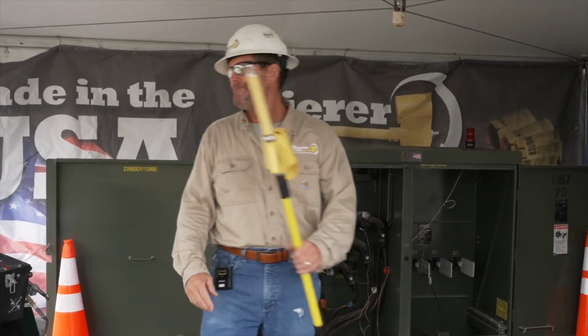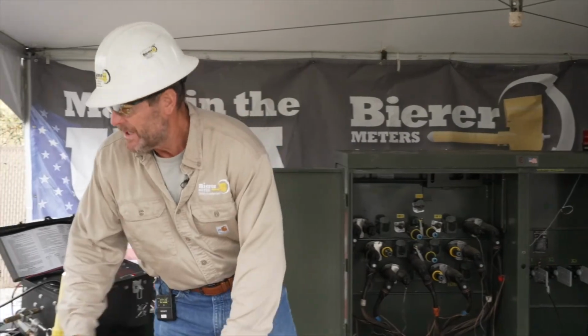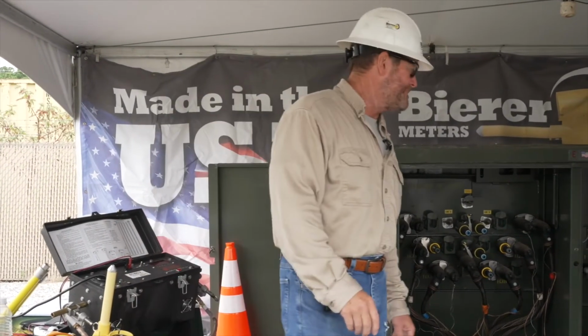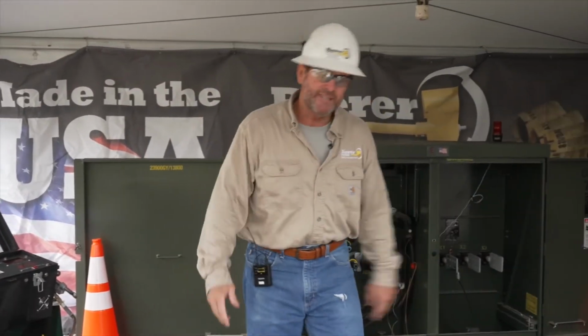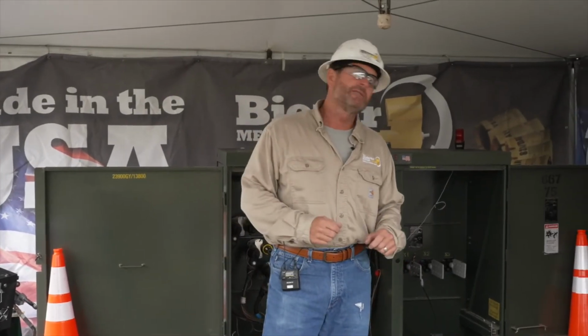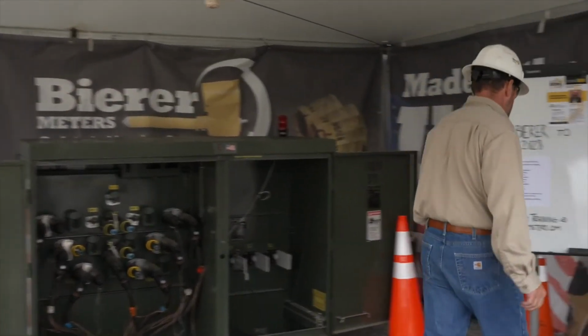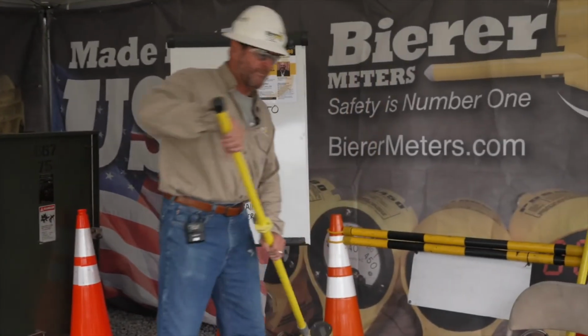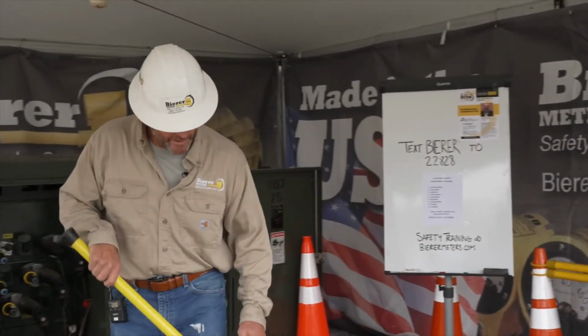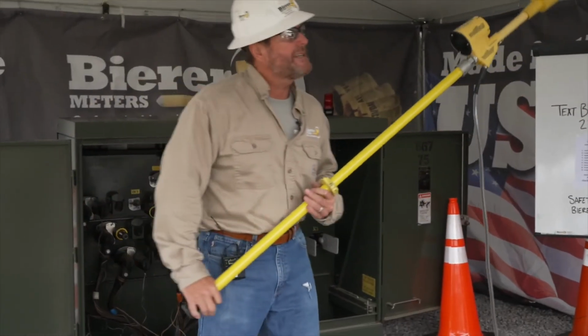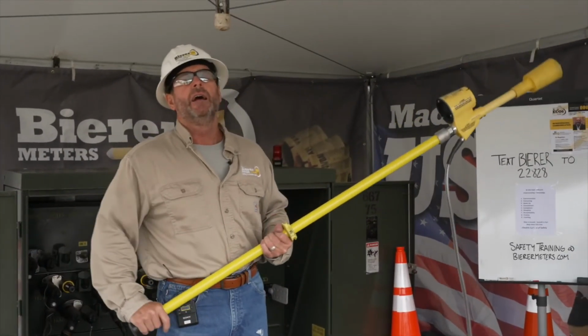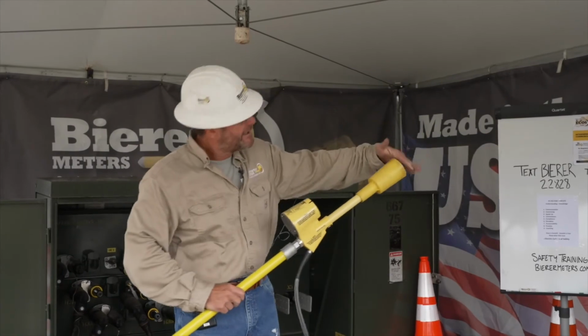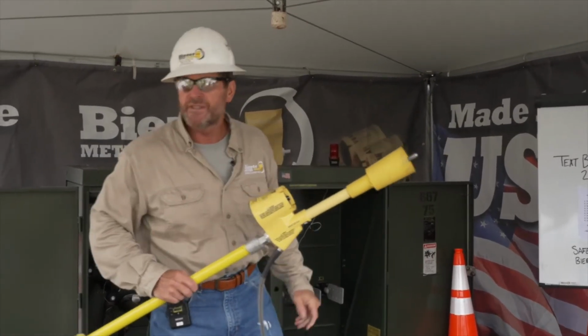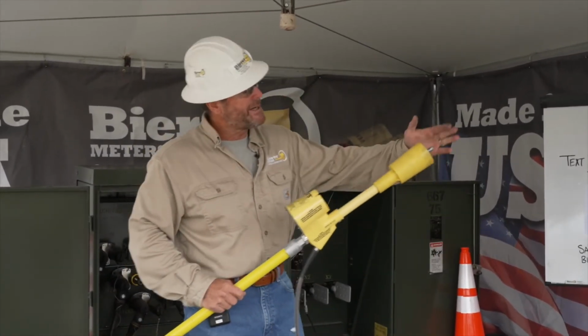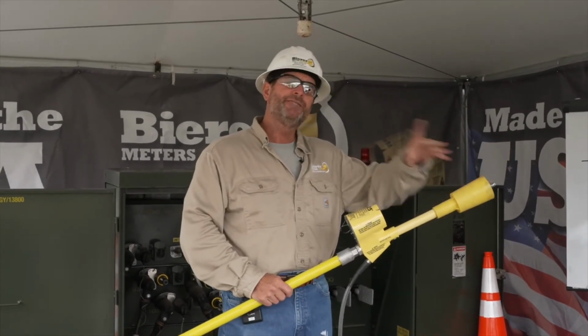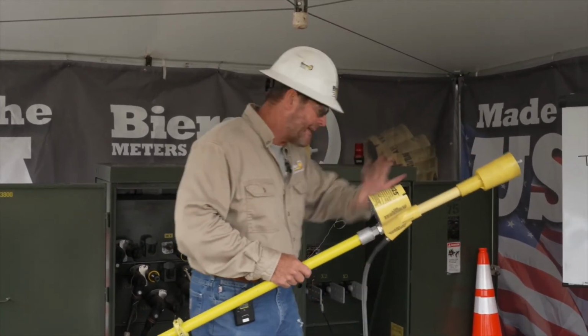What happened is these folks—I don't want to pick on this same state every time, so I won't say the state—they had a PD 25, true story. They went to that substation and looked at that hot bus. They didn't have a bushing adapter on, it was a straight probe. But they had a hot bus, and they made contact with it. Check this out: corded, phase to ground.